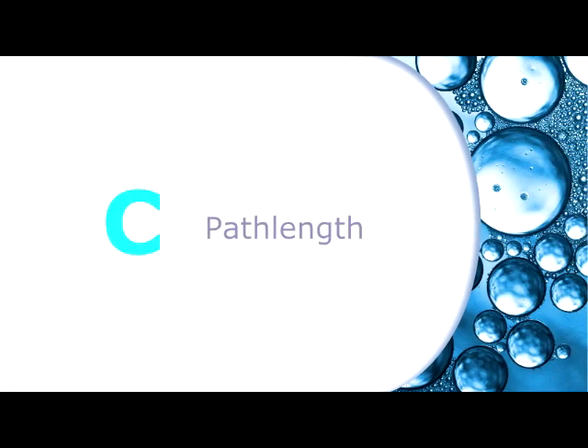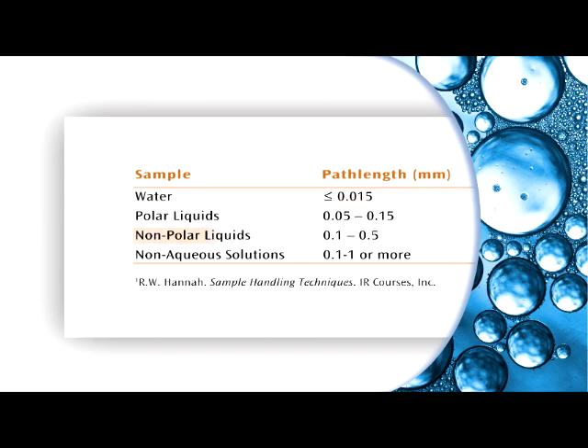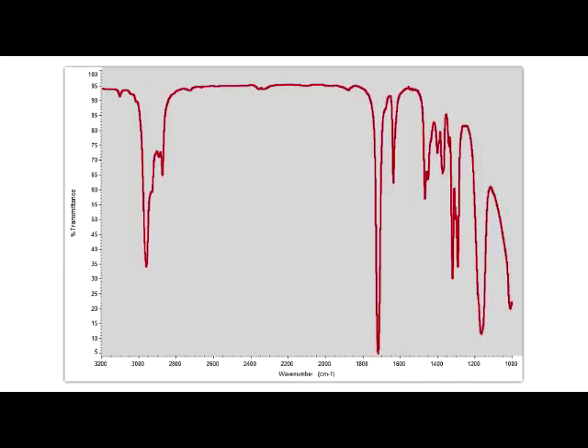The optimal path length is sample dependent. As a rule of thumb for measurements in the mid-infrared, typical path lengths for polar liquids are 50 microns to 0.15 millimeters. For water, 15 microns or less. Non-polar liquids from 0.1 to 0.5 millimeters, and non-aqueous solutions from 0.1 to 1 millimeter or more. Generally, it's desirable to have the absorbance bands of interest range from 20 to 80% transmission.